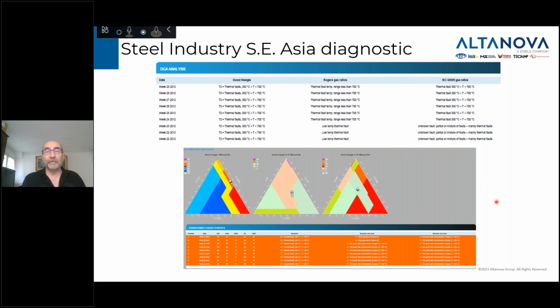Now, when you put them into the Duval triangle, because the Duval triangle, as I mentioned earlier, has more triangles developed to pinpoint the fault more specifically. When you use Duval triangle LTF, low temperature fault, number 4 and number 5, it gives you mostly, unfortunately, I apologize, this is very difficult to read. What it tells you is mostly it seems that you have some kind of carbonization happening in that transformer. So you have a low temperature fault, mostly much closer to 300 degrees C, and you have some kind of insulation degradation that's happening.